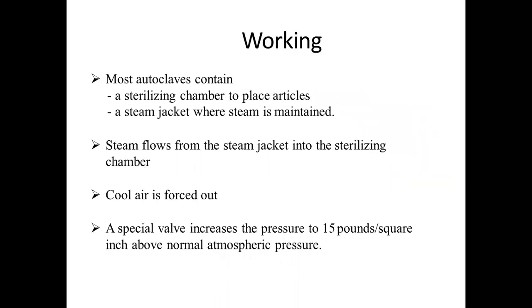Then working. Most autoclaves contain a sterilizing chamber to place article. A steam jacket where steam is maintained. Then steam flow from the steam jacket into the sterilizing chamber. So cool air is forced out. A special valve increases the pressure to 15 pounds per square inches above normal atmospheric pressure.